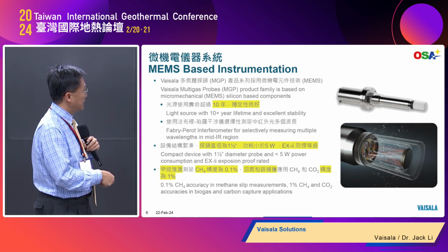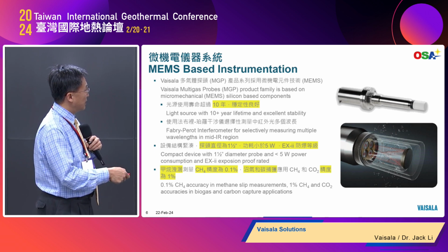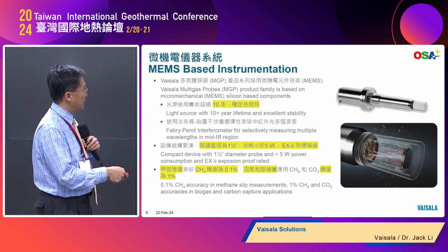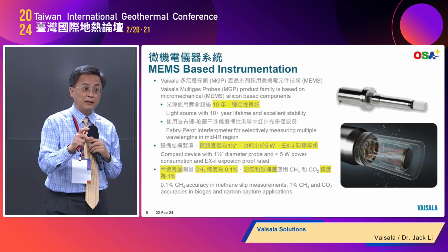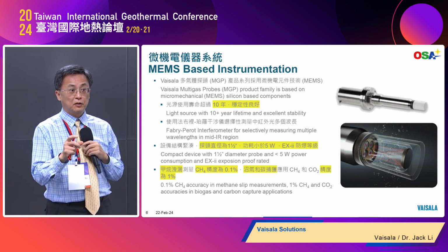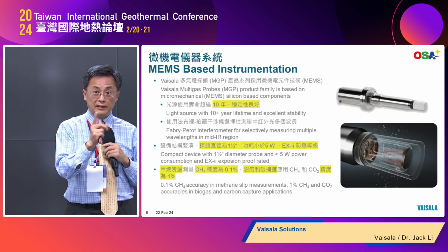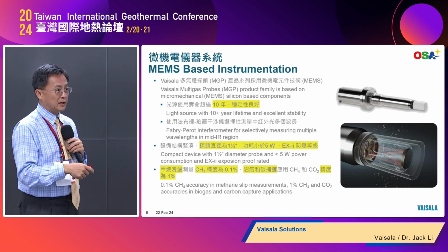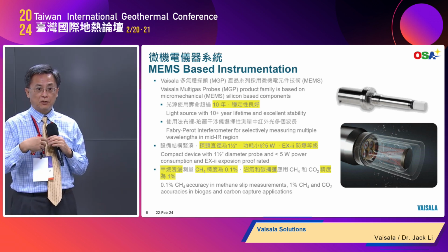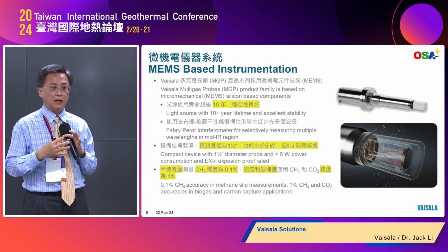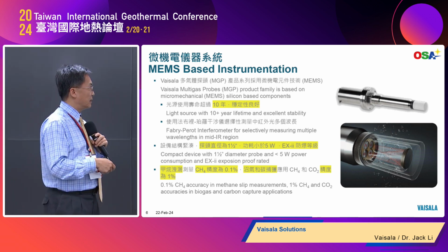It's fairly compact. The head is this part here in the white cap. The white cap is actually a Teflon filter, because you don't want to dirty the optics inside. It's a hydrophobic cap, so no moisture, no condensation can happen inside.